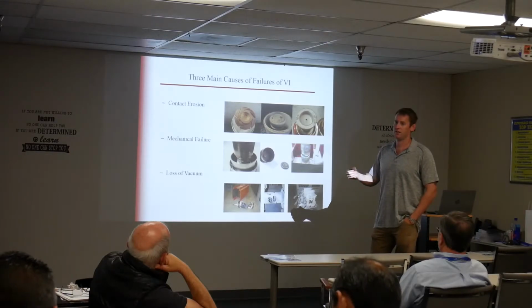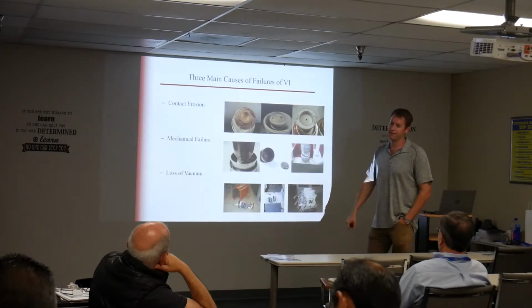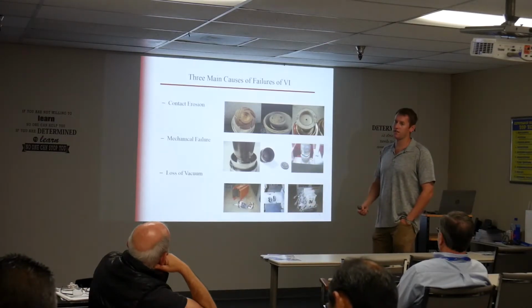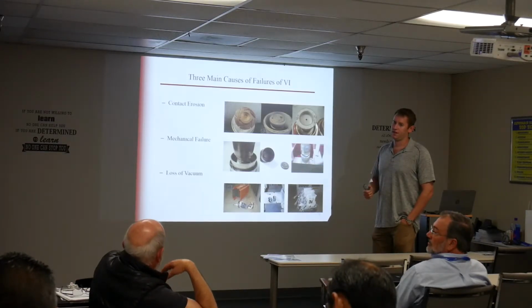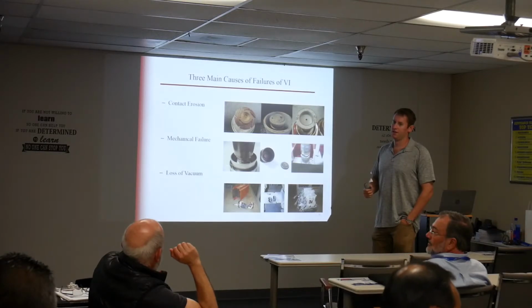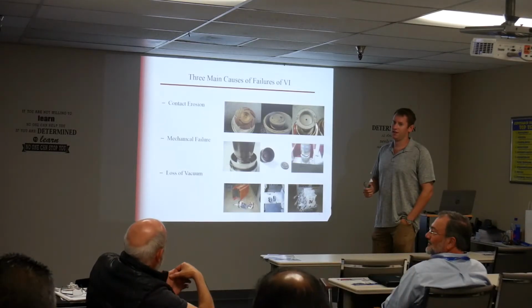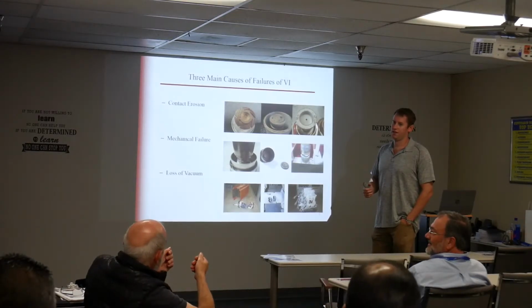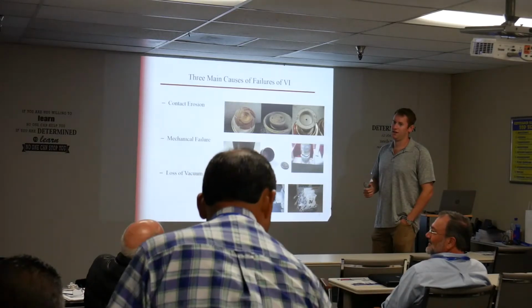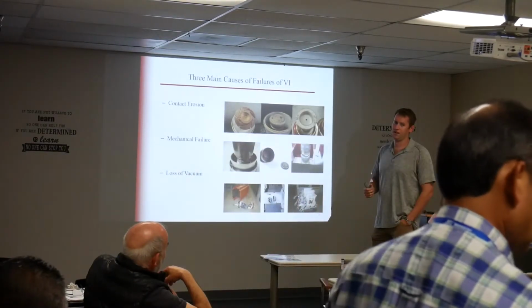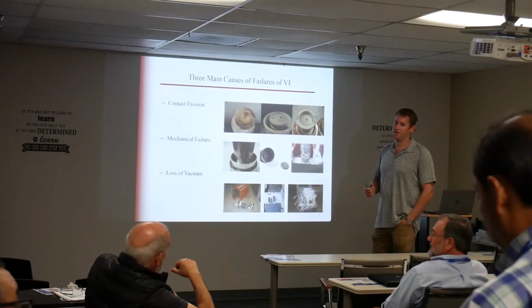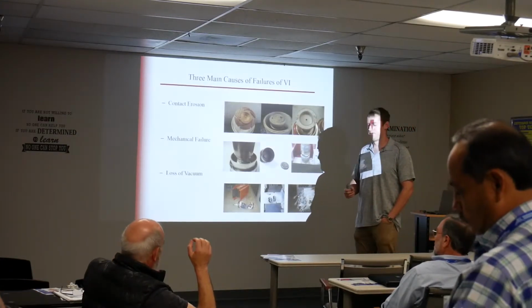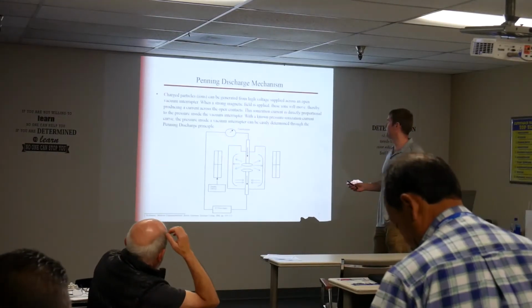But I've had cases where utilities went out to rack out breakers, not knowing one bottle's bad, and it makes an arc flash. I had it happen in my home on a water heater. I opened the breaker outside, and I was doing some work inside, and I checked phase to phase. I didn't check phase to ground. The phase was still live. I thought, what the hell is that? And I got phase to ground.